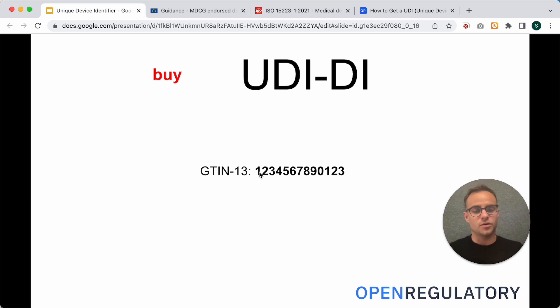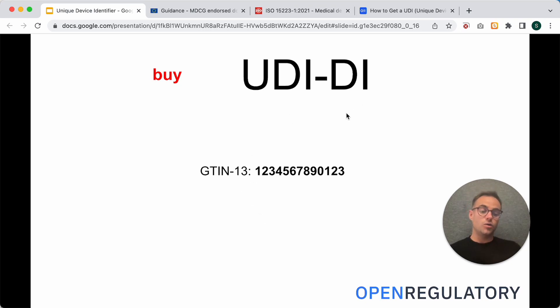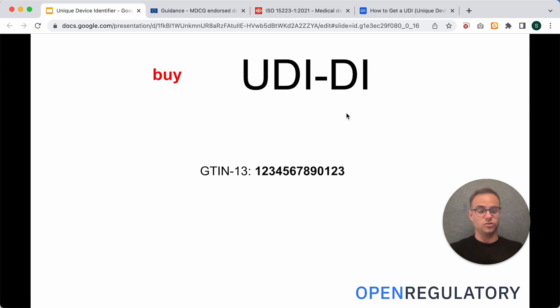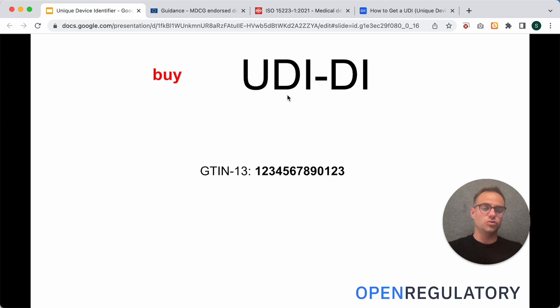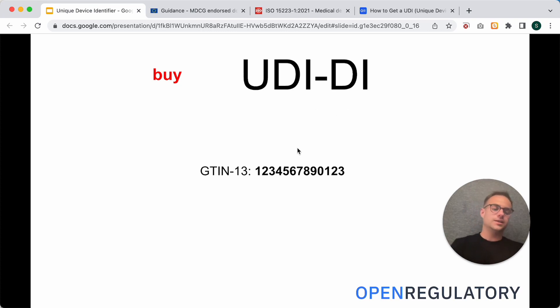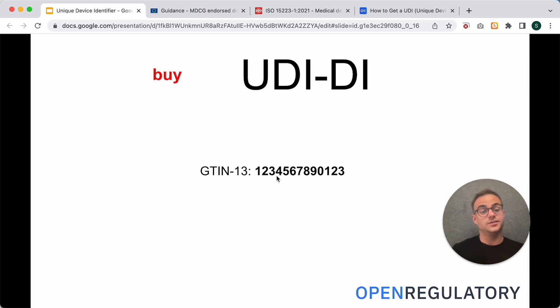So, keep in mind here that this UDI-DI only changes when you make major changes to your device or your software, and then you would need a new UDI-DI. So, it's very unlikely that you will ever need 1,000 UDI-DIs with the software.